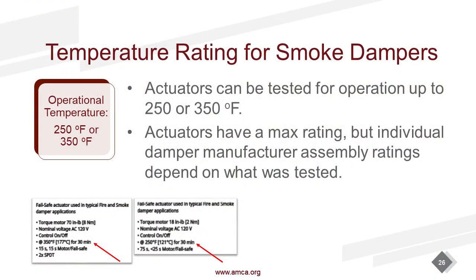So we did talk about that operational temperature rating again for the smoke damper. So again, that's that max rating that the temperature can operate. At least one more time. Whenever we talk about fire smoke dampers, the over specification of dampers does not increase the safety of your building or the performance of your system. It costs your owner money, period.